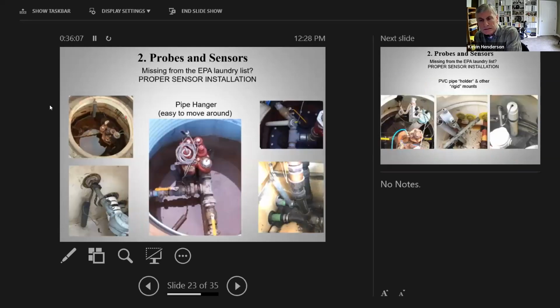The little hanger that comes on the standard 208 probe gets hung off a lot of different things. The pipe hanger really is used by a lot of guys to be able to pick the sensor up off the bottom of the sump and get it out of the water or whatever's caused it to be in alarm. Right? You see this all the time. So if you're an owner operator in particular, go out, look at your containment sumps and see where your sensors are. If they are not sitting at the bottom of the sump, and if they are not vertical, then they are not in compliance.